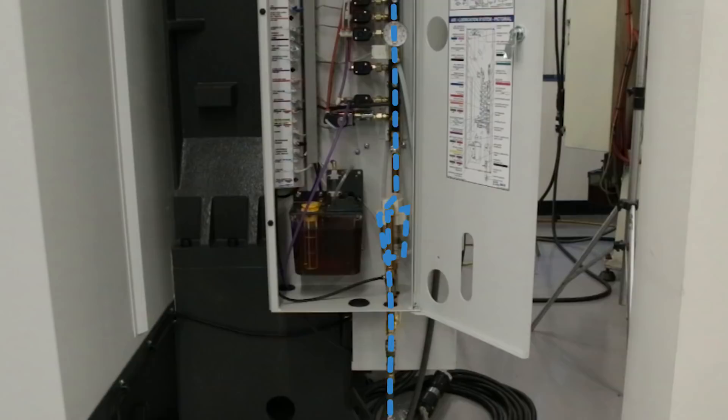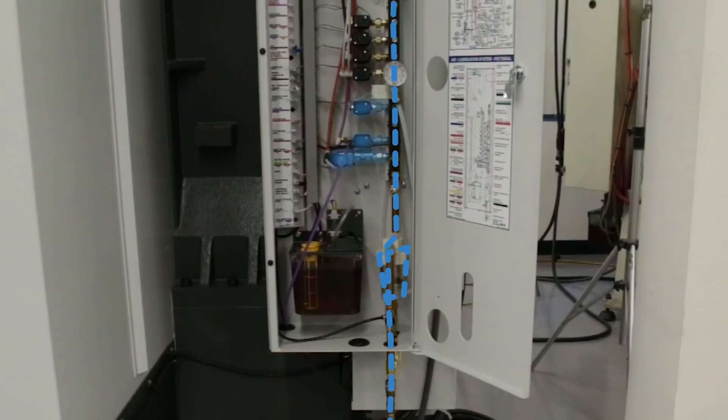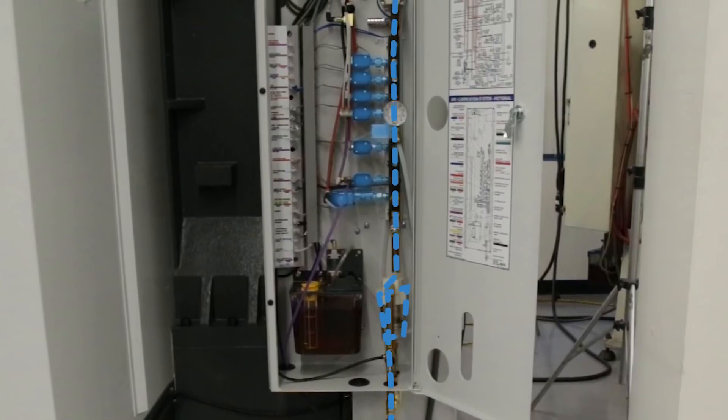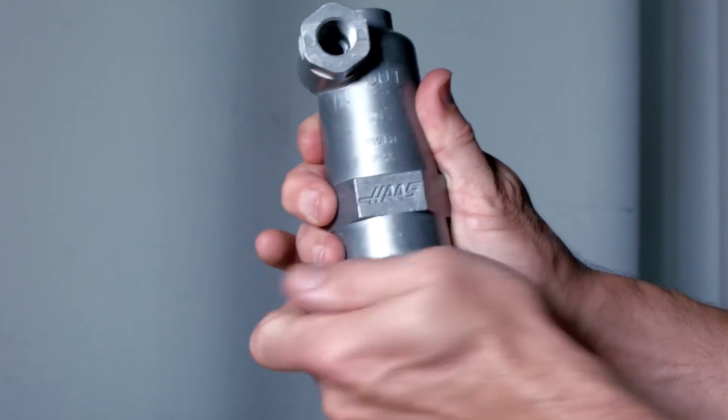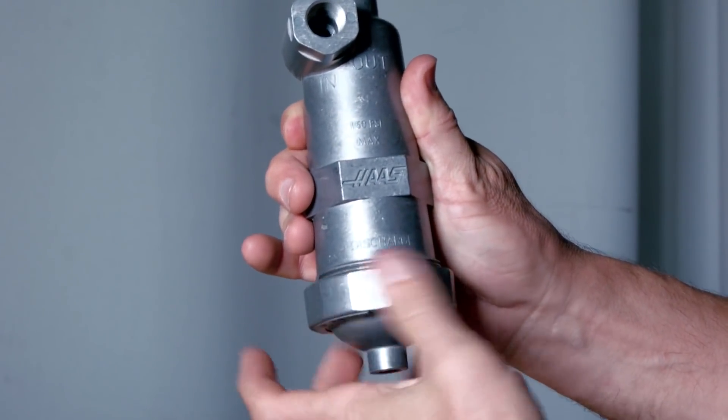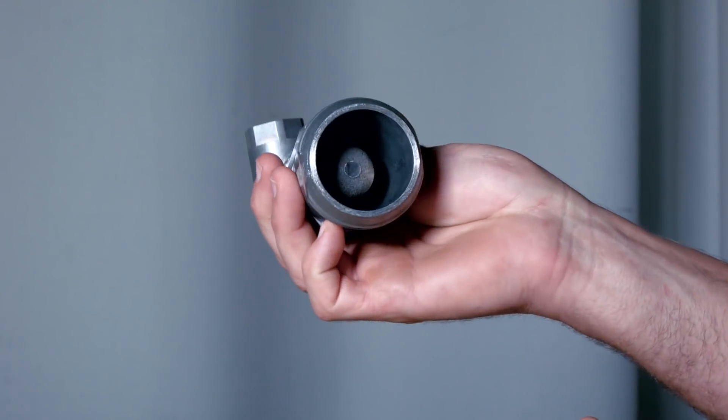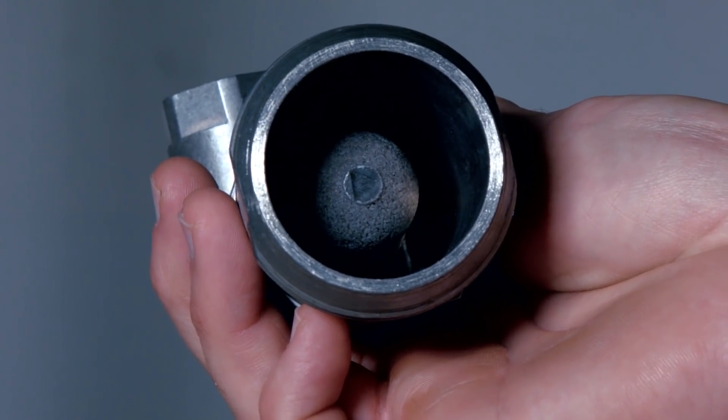As you can see, your incoming air feeds directly into this manifold and right into these solenoids. Be sure and check this filter regularly since this is the last line of defense before air gets into your machine. Not only do you want to clean any debris out for obvious reasons, a clogged filter might also be restricting the airflow to your machine. Whether it's water or debris, poor air is a quick way to have your machine down and needing repairs.